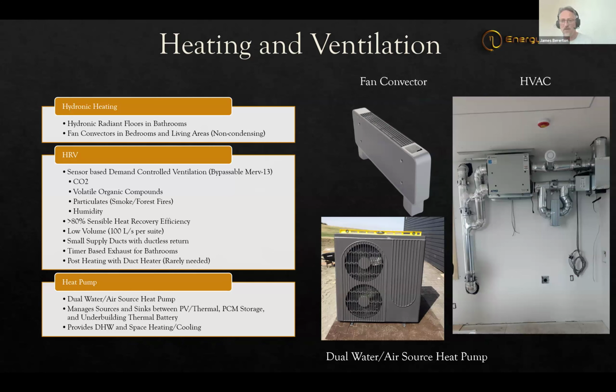You can see the HRV in the middle, the Atmo 200E, and we've got 5 different damper valves so we can put it into recirculation mode, which we want to do if there's a forest fire—running it through a MERV 13 filter or not. We don't want to go through the MERV 13 all the time because it clogs up quickly, and you only need it for the really fine particles. So when we sense particulates going up, say from a forest fire, we run it through the MERV 13 and recirculate—we're not trying to clear the whole atmosphere, just the house. If there's a CO2 demand call, it'll switch to bring in fresh air, and once that's cleared, it goes back to filtering out particles.